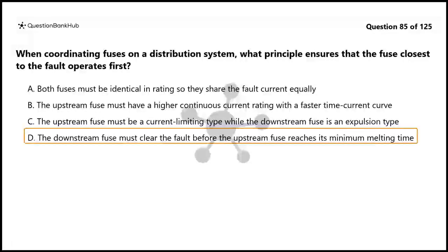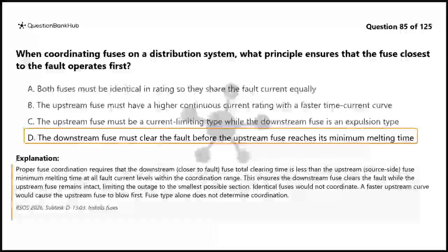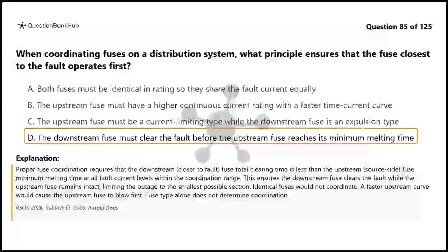The correct answer is D. Proper fuse coordination requires that the downstream, closer to fault, fuse total clearing time is less than the upstream, source side, fuse minimum melting time at all fault current levels within the coordination range. This ensures the downstream fuse clears the fault while the upstream fuse remains intact, limiting the outage to the smallest possible section. Identical fuses would not coordinate. A faster upstream curve would cause the upstream fuse to blow first. Fuse type alone does not determine coordination.